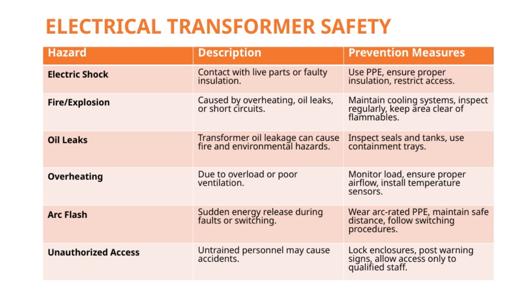Oil leaks are another concern, especially since transformer oil can cause both fires and environmental damage. Preventative measures include inspecting seals and tanks regularly and using containment trays to catch any leaks. Overheating is a common issue, often caused by overloads or insufficient ventilation. Monitoring load levels, ensuring proper airflow, and installing temperature sensors can help us catch problems early before they escalate.